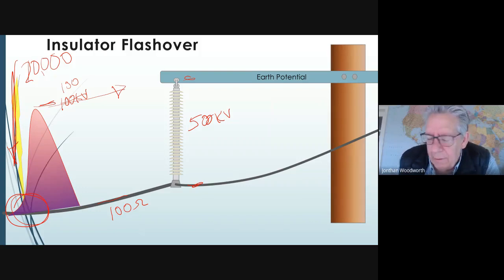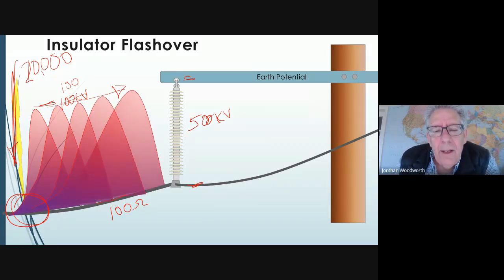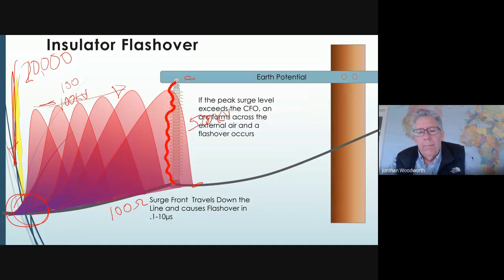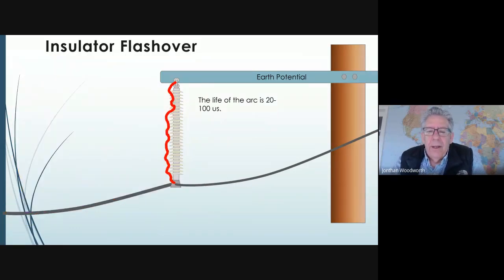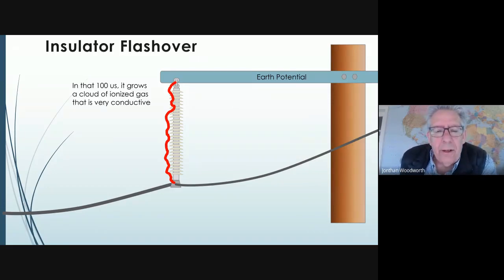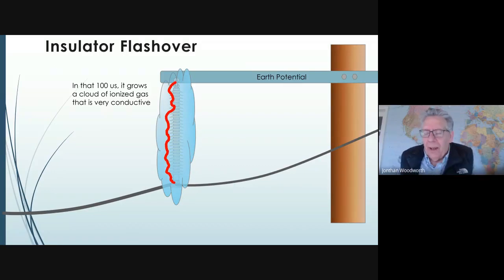Guess what's going to happen? It comes down the line, it gets to this insulator, and boom, you have a flashover. Now this flashover is quick and fast. Its life cycle is 20 to 100 microseconds. So it's there and then it's gone. And before it goes, though, it grows this ionized gas envelope around the insulator.